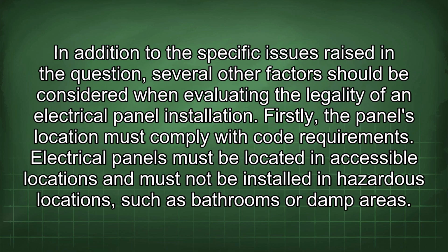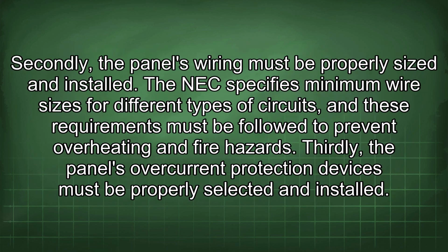In addition to the specific issues raised in the question, several other factors should be considered when evaluating the legality of an electrical panel installation. Firstly, the panel's location must comply with code requirements. Electrical panels must be located in accessible locations and must not be installed in hazardous locations such as bathrooms or damp areas. Secondly, the panel's wiring must be properly sized and installed.